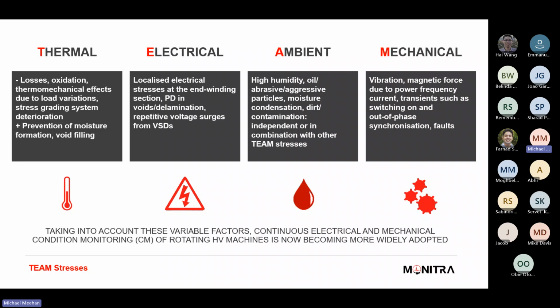Temperature plus air in air-cooled machines leads to oxidization, which means brittle insulation and potential delaminations. Thermomechanical stress due to load variations: copper expands more than the insulation, with higher thermal expansion coefficients, and after many load cycles the adhesion may break. With VSDs, frequent short duration voltage pulses lead to temperature tip-ups. They're all challenging and create these temperature issues within the machine. And stress does degrade the stress grading of the insulation, especially in VSD machines, if the VSD machine is maybe not designed properly or has issues during the design process.